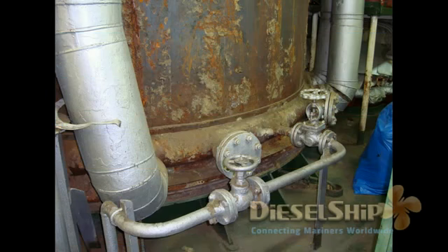So here are some pictures of boilers which I worked on. The boiler shown over here is completely ripped off. We were doing some retubing work with some Greek fitters, so this picture was taken at that time. Let me explain some components which are visible in this picture. This is the mud ring, and these are the downcomers.